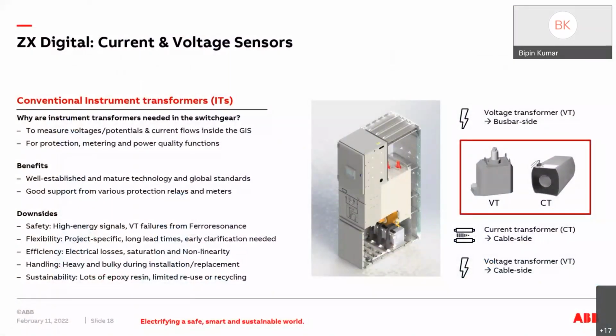Yes, we have the sensors available which can work with a switchgear. Those are forming the basis of smart automation and control and the monitoring and diagnostics features of those switchgear. Because these days a lot of thought is getting driven towards preventive and predictive maintenance, or rather condition-based maintenance to be true. So one thing we have done is replacing the conventional current and voltage transformers with current and voltage sensors. The conventional current and voltage transformers, yes, we have been using them for decades now, and they are doing their work. But there are some potential disadvantages: CT sometimes fails because of saturation, VT sometimes fails because of ferroresonance, and these are fixed to certain ratios.